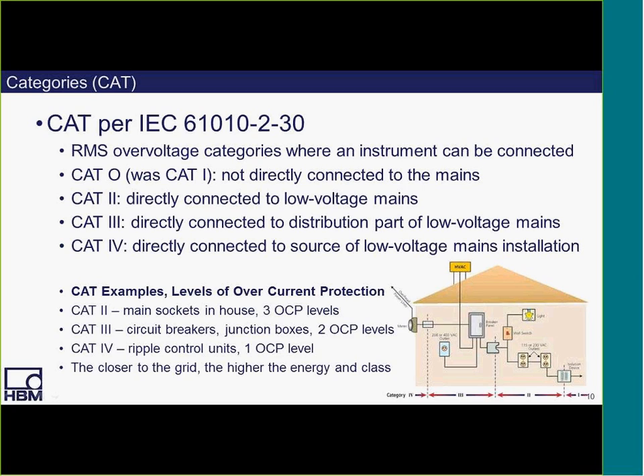Now, the IEC has established a list of categories, or CAT for short, which identify RMS overvoltage levels or categories where an instrument can be connected. So CAT 0, which used to be called CAT 1, is basically not directly connected to the mains. CAT 2 would be directly connected to low voltage mains. CAT 3, directly connected to the distribution part of low voltage mains. And CAT 4 is directly connected to the source of low voltage mains installation. As you can see in the diagram on the bottom right, the closer to the grid you get, the higher the energy and the class.